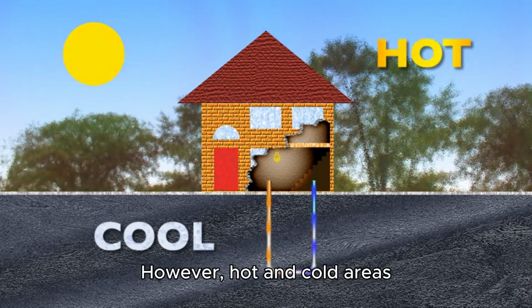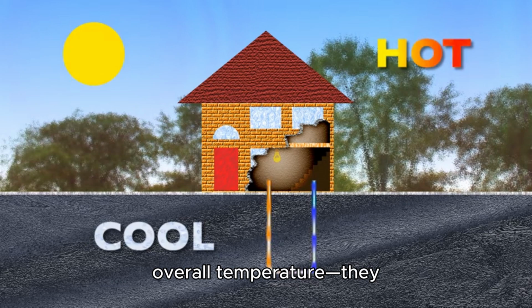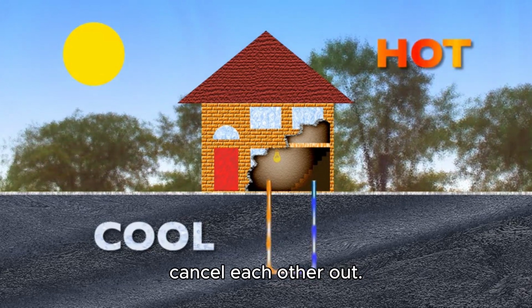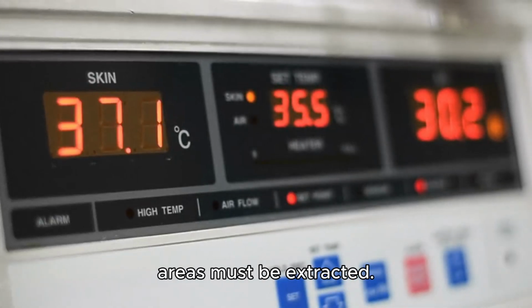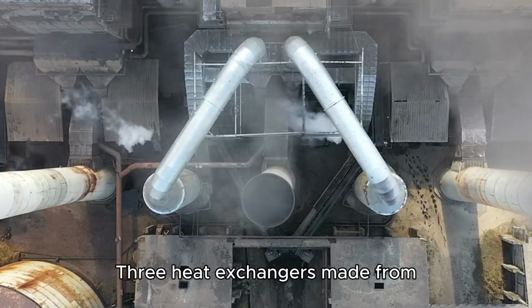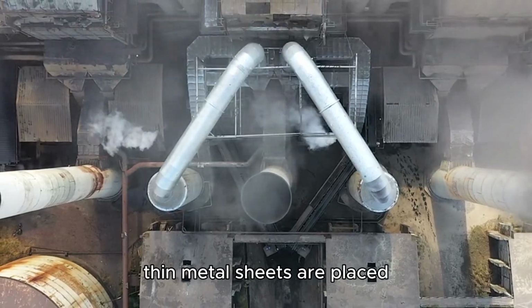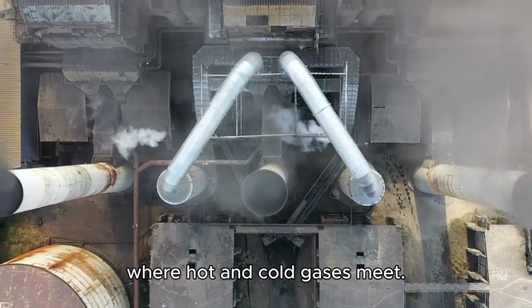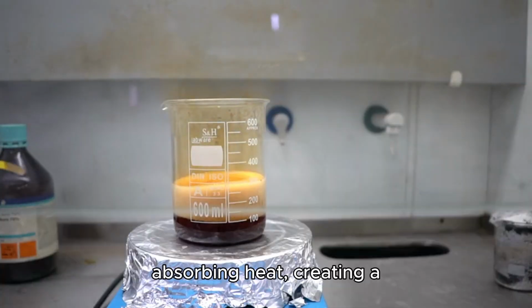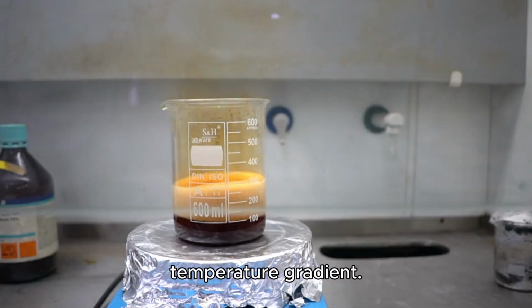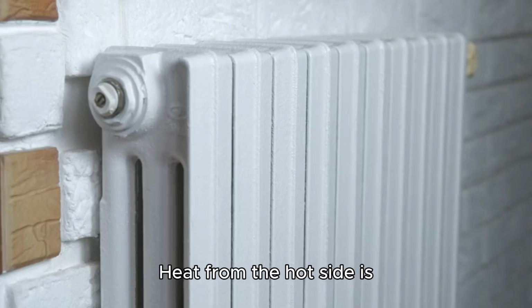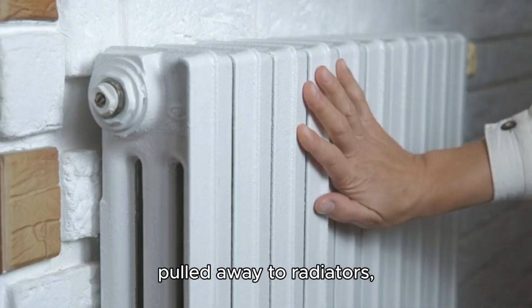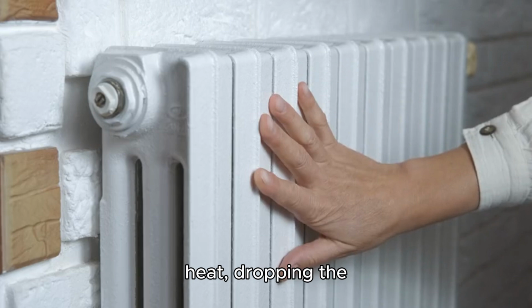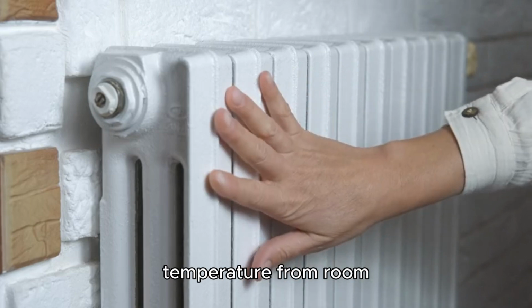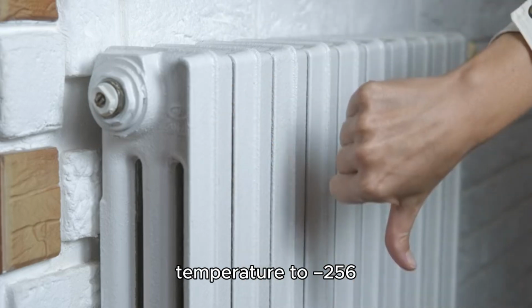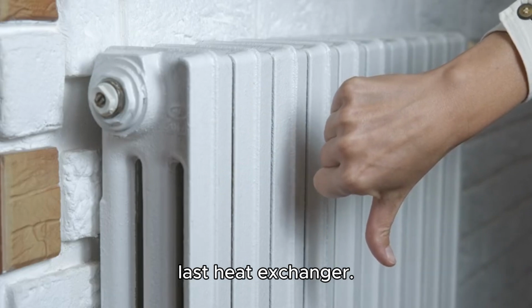However, hot and cold areas alone don't change the overall temperature, they cancel each other out. To cool down, the hot areas must be extracted. 3 heat exchangers made from thin metal sheets are placed where hot and cold gases meet. These allow gas to pass while absorbing heat, creating a temperature gradient. Heat from the hot side is pulled away to radiators, while cold areas lose heat, dropping the temperature from room temperature to minus 256 degrees Celsius at the last heat exchanger.